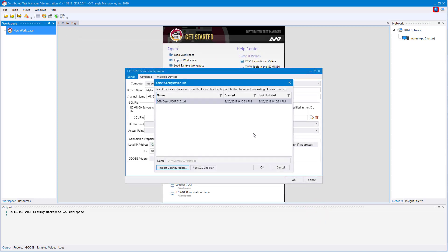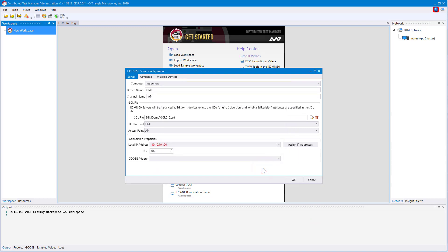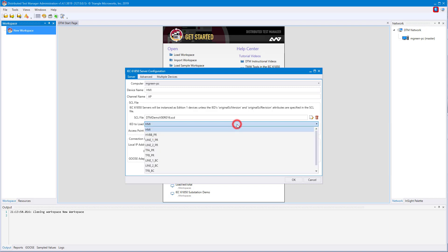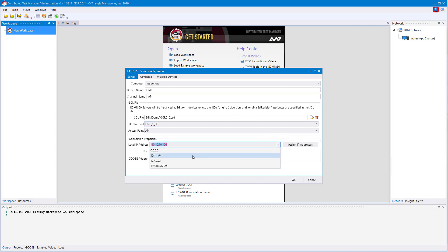Now that that file has been imported, you can click OK. You will see that all the configuration options are now filled in. If your SCL file is an SCD file or contains multiple IEDs, you can click this drop-down to select which IED you would like to load. You can also go and change from the default IP address found in the file to something that is on your computer.